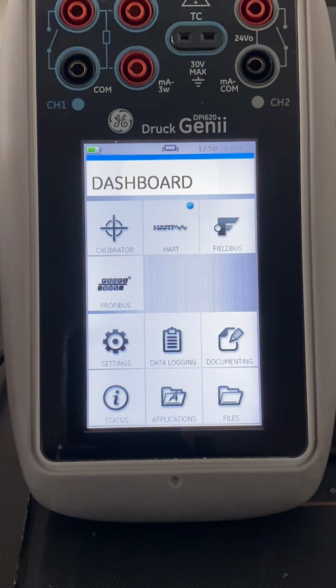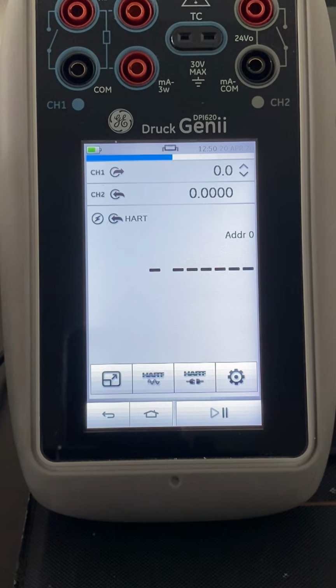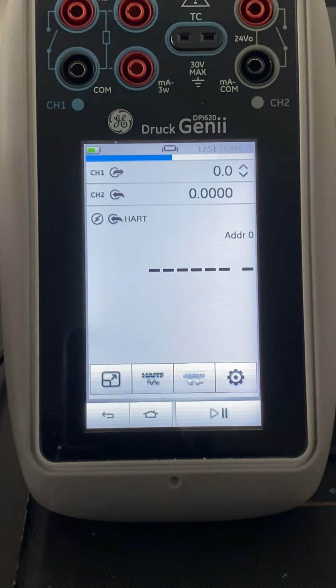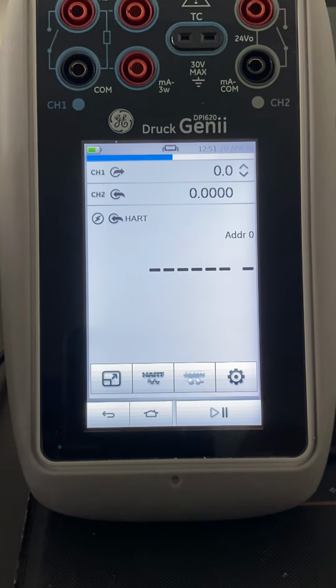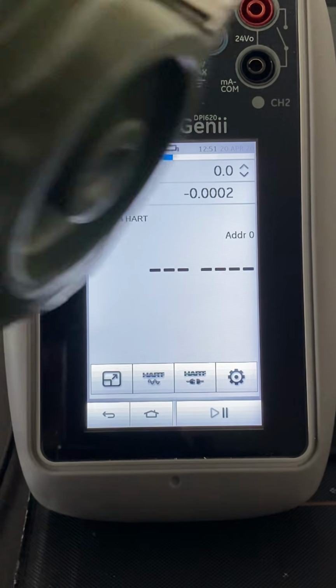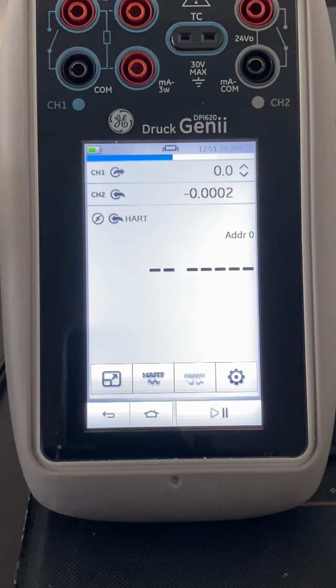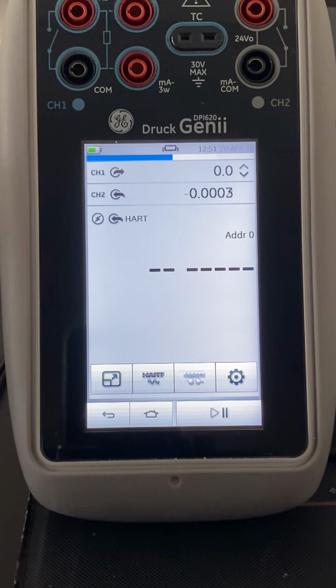To go to the HART function, this is the icon, we press on that, and this is our HART menu. We can set up channel 1 and channel 2 to the parameters we want. As we know, the HART communication requires a HART resistor and requires a power supply for the transmitter if the transmitter is not already powered from the network. So we have a couple of functions we need to set up. In my case, my transmitter is disconnected from the network. There is no resistor in the leads and there is no power supply. So I have to add a HART resistor and I have to power it up.